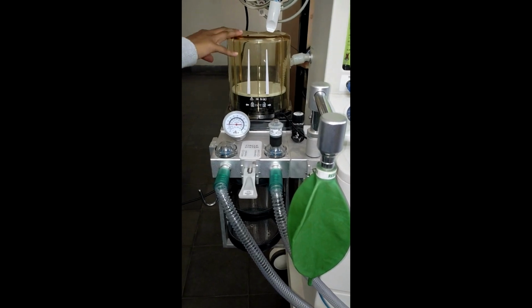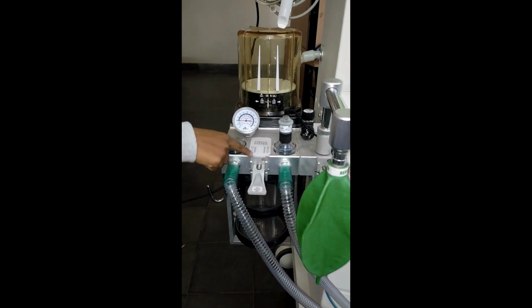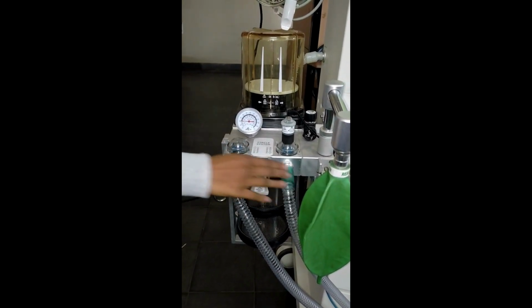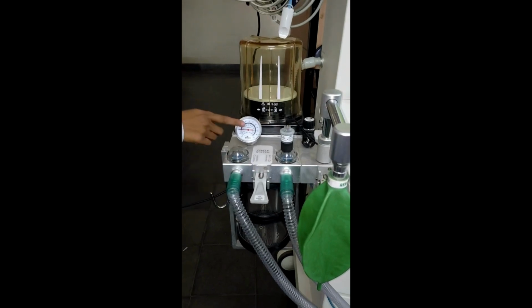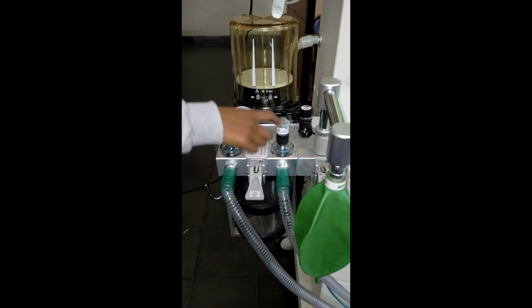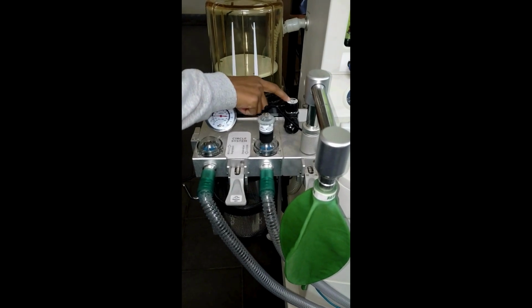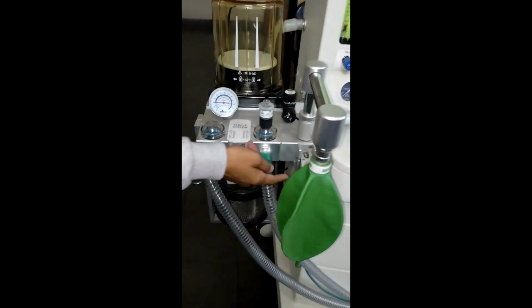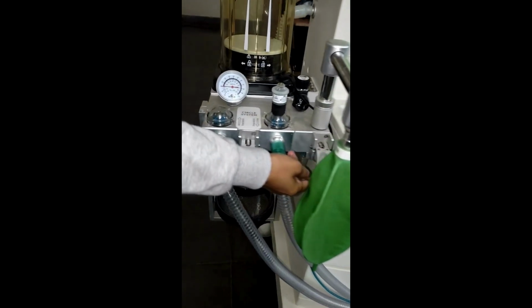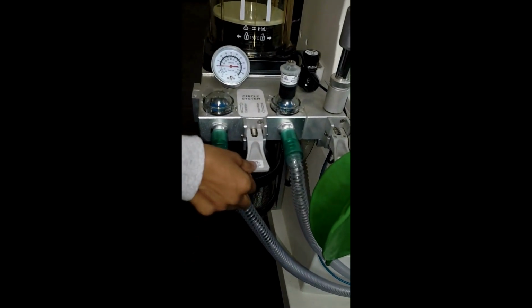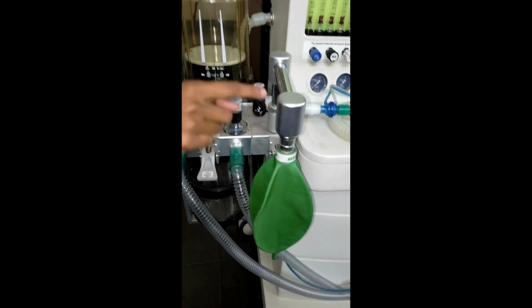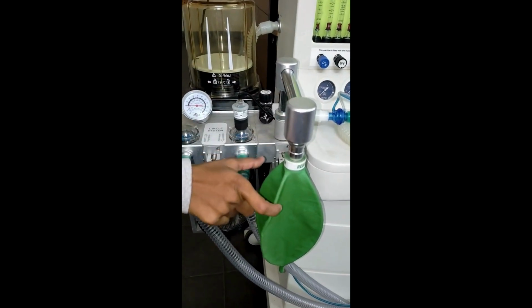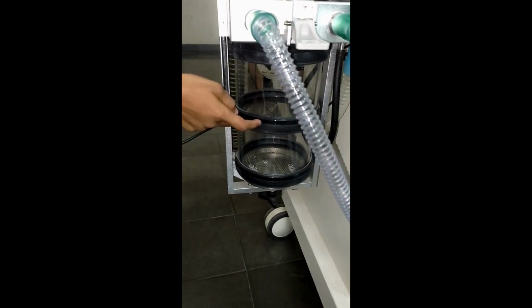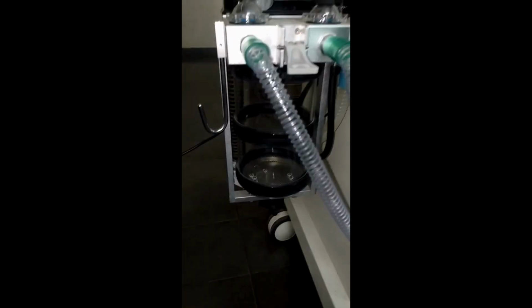Here we have the bellows assembly. Here we have the circle system, in which we have the inspiration port and expiration port, pressure gauge and the O2 sensor. And here we have the airway pressure limiting valve. Here we have the vent or bag switch. Here we have the absorber on off switch. This is the mounting arm to which we connect the reservoir bag. We have the canister which holds the soda lime up to 2 kg.